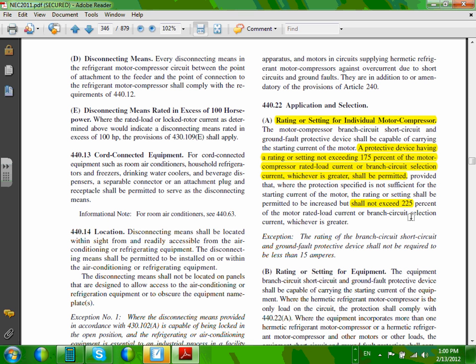But the chiller, we actually didn't size it. It's already sized for us in the cut sheet. Had it not been sized in the cut sheet, then we go and we multiply it by 1.75. That makes sense. Times the rated load amps, which is full load current. Yeah. They call them rated load amps.